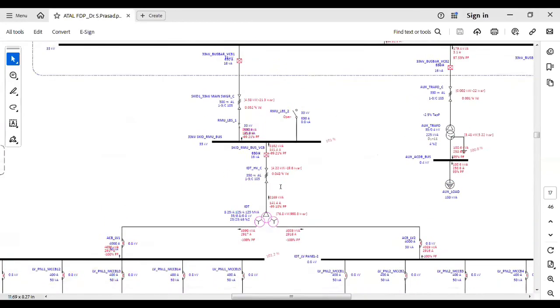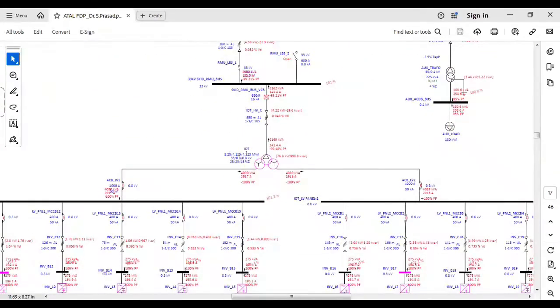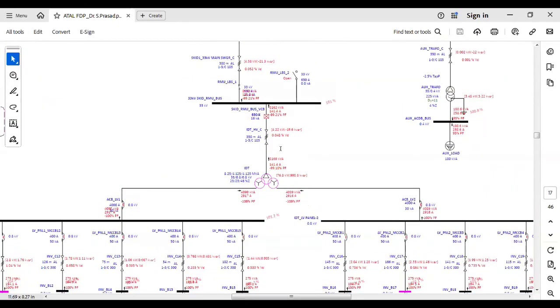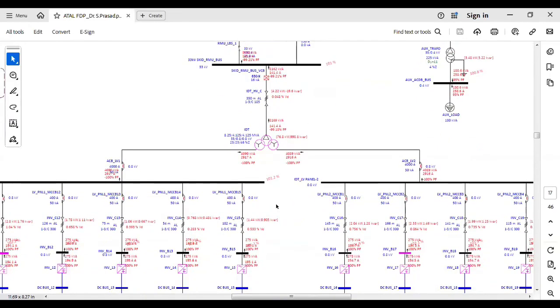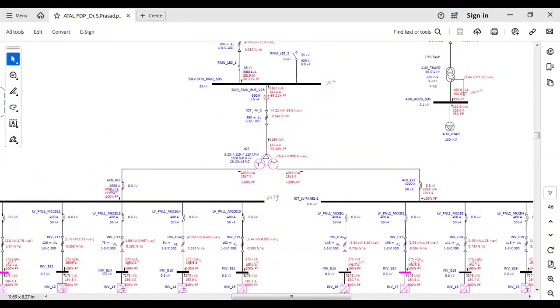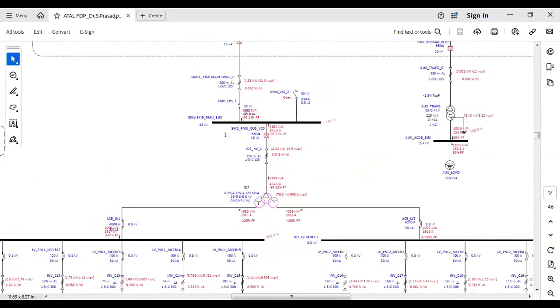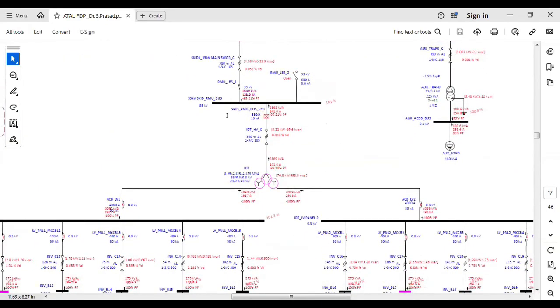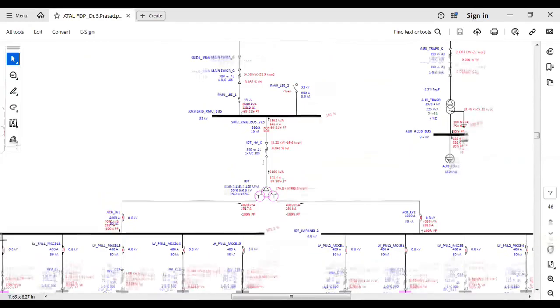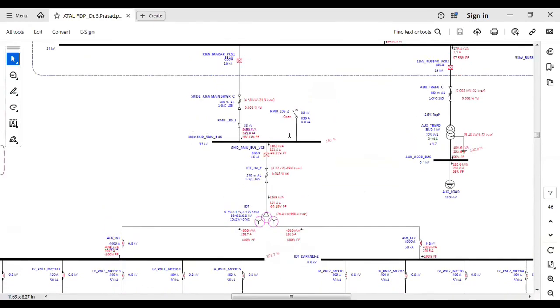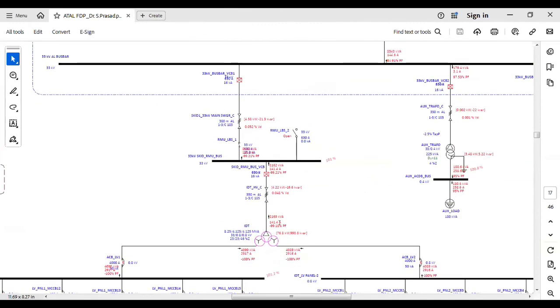We are conducting the load flow to check whether the transformer is getting overloaded, which cables are getting overloaded, and what the voltage is at all the buses. That is called load flow analysis. These are the two LT panel buses, and this is the RMU bus, the 33 kV skid RMU bus. This is a skid solution. Since the transformer is converting 0.8 kV to 33 kV, it is connected to the 33 kV RMU bus.